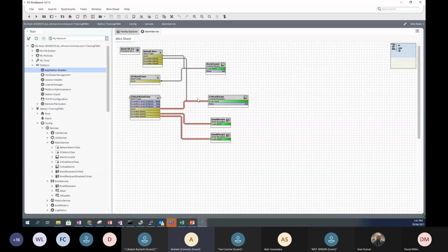and then reroute through and back to the FX servers itself. Yes. So when client try to acknowledge the alarm from the FX server's main alarm notifications, the thing is sometimes we encounter that the alarms do not flush through all the FX80, which means there's some delays and there's some leftover alarms under the FX80 itself, and then after maybe another 5 minutes or 10 minutes the alarms come back and pop up again at the FX server's level.